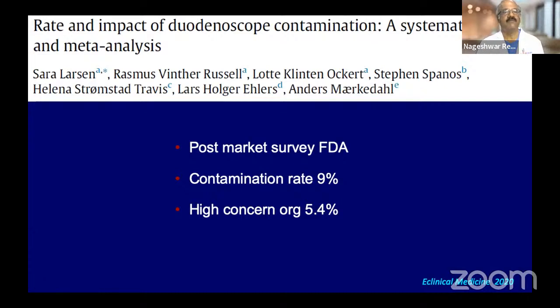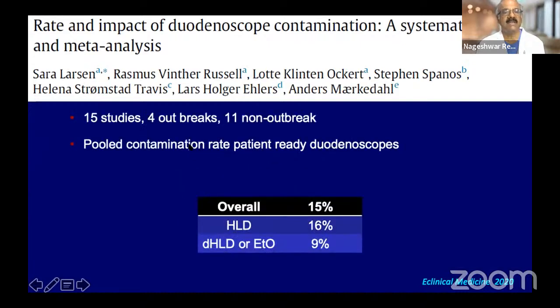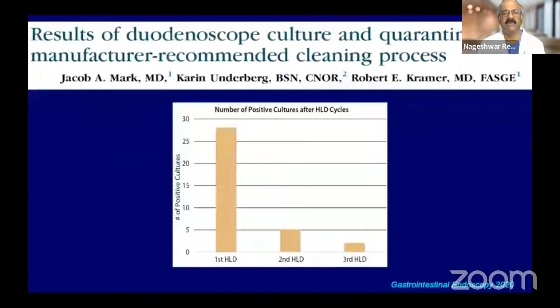The post-market survey, which the FDA forced the companies to do, showed a contamination rate of 9% with a high-concern organism, which I mentioned earlier, 5.4. But if we actually look at a recent meta-analysis of the pooled contamination rate of patient-ready duodenoscopes, you will see that it's actually much higher. Even after high-level disinfection, it's about 16%. And even after double disinfection or ETO, it's still 9%, which means that it's extremely difficult to really remove all the infections from these scopes.